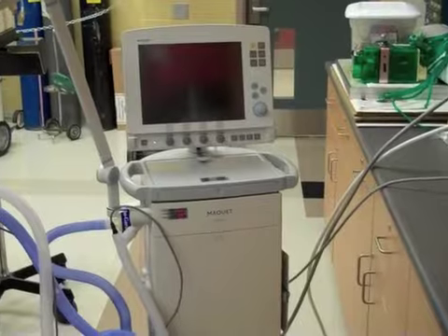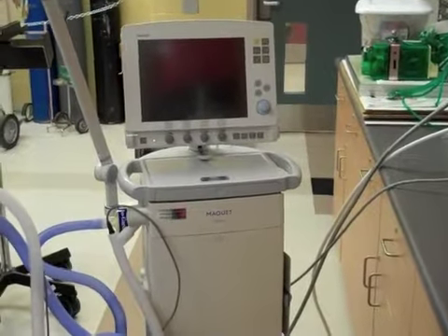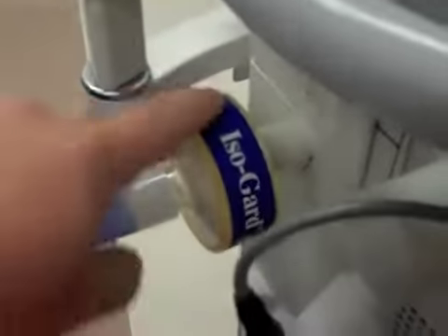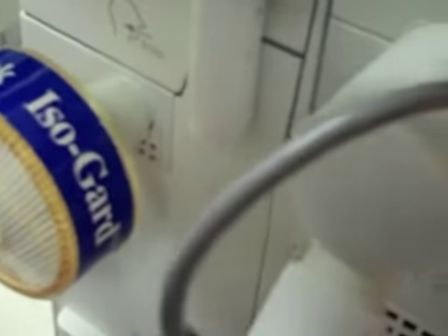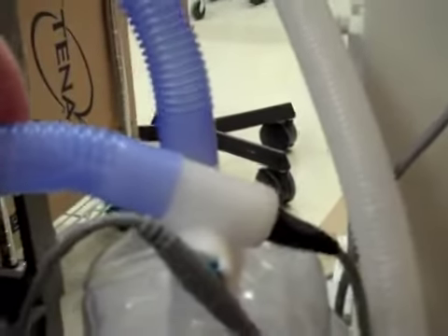Okay, so this is the Servo-i, and we're going to go through a device check and circuit check. You'll notice this one's already hooked up, so I've got an inspiratory filter, and I think even on the Servo-i it says inspiratory, expiratory, so if you're ever stuck in the OSCE: inspiratory filter, short tubing going to your heater chamber. Heater chamber then is going to hook into your other side of your inspiratory tubing, which is going to bring the gas to your patient.